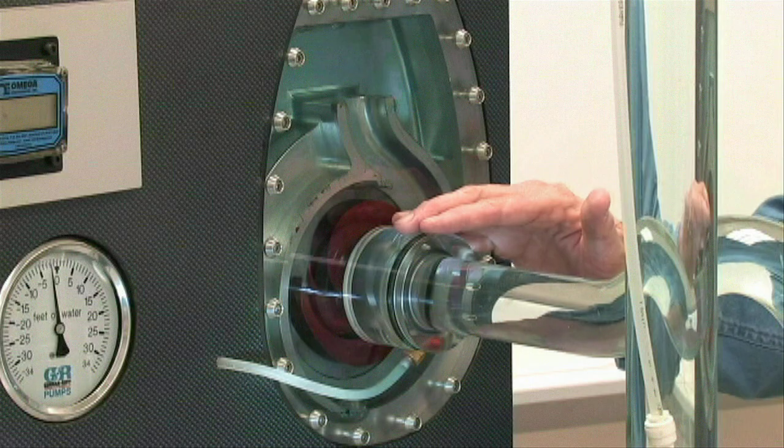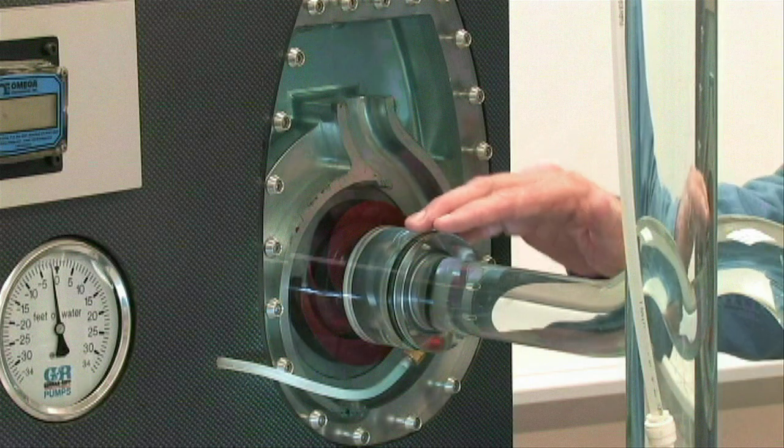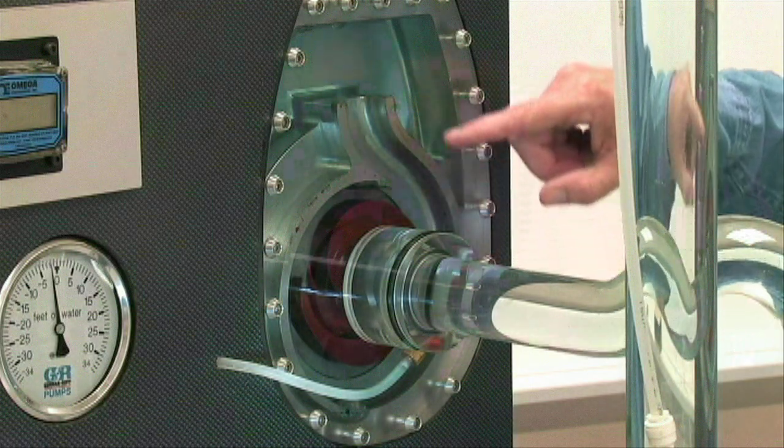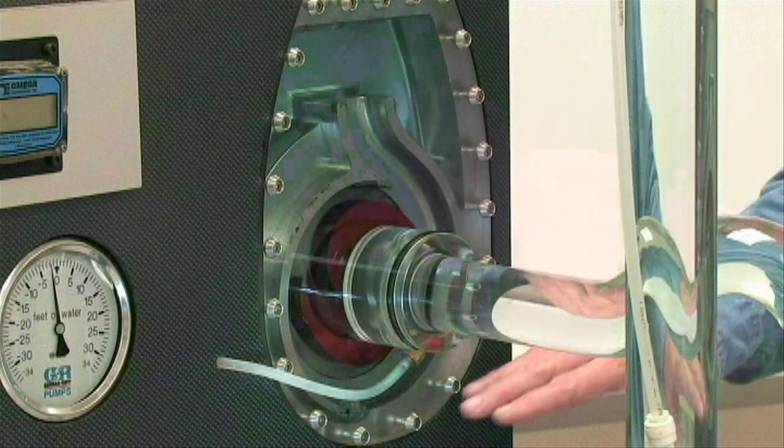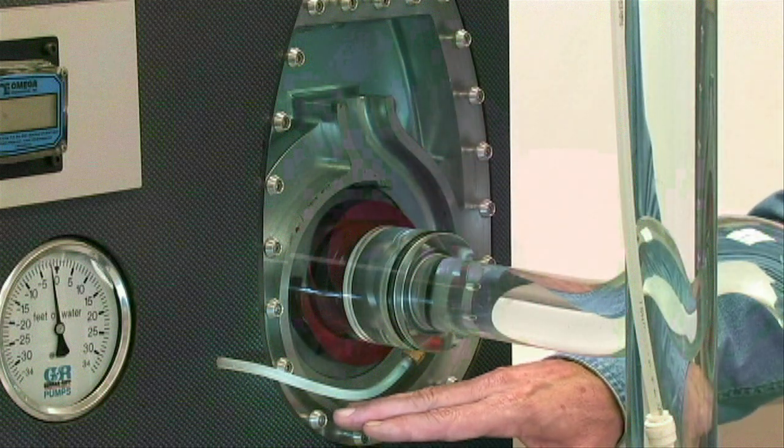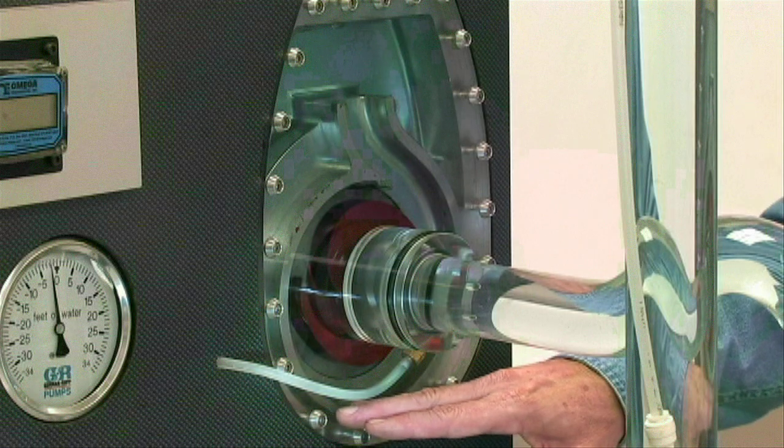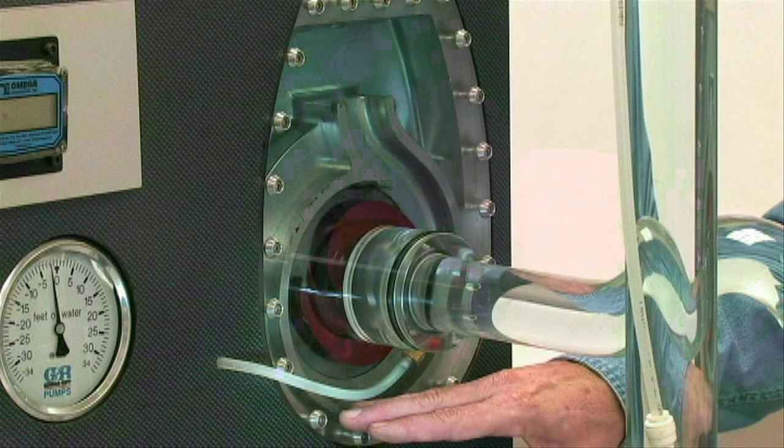And finally, recirculation. During priming, we recirculate water through the volute casing to create that low pressure at the eye. By plugging up the recirculation port, we fail to recirculate water within the casing and fail to prime.